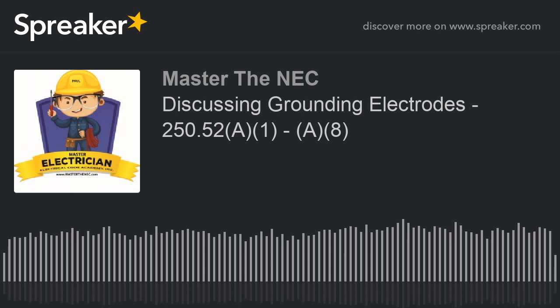Okay? All right, so now let's go on to A7. Now, A7 is the plate electrode. So we get the parameters for what qualifies for a plate. It says each plate electrode, and literally as it sounds, it's a plate, okay? And that's it. I'll read it for you in a second so you understand what we're dealing with. It says each plate electrode shall expose not less than 2 square feet of surface to exterior soil. Okay, so it's a fairly good sized plate.